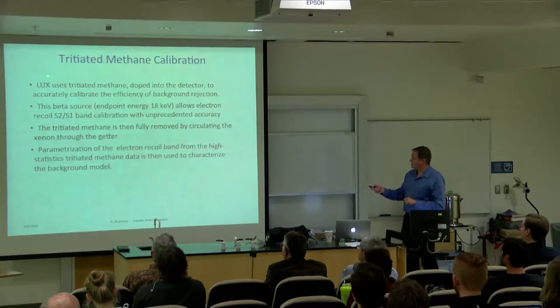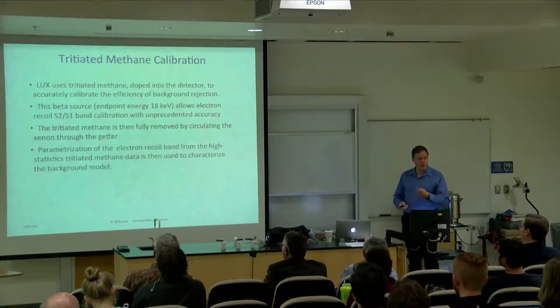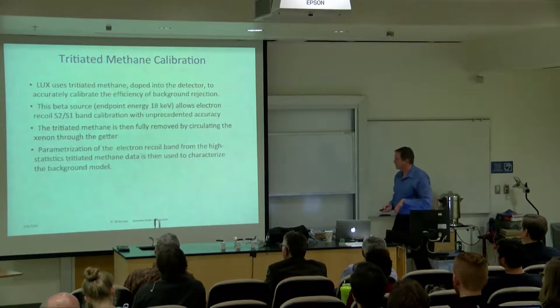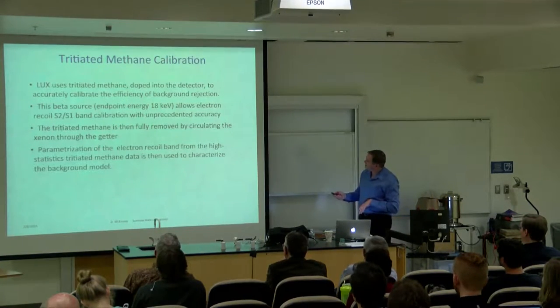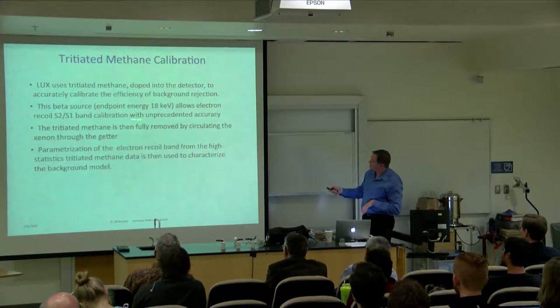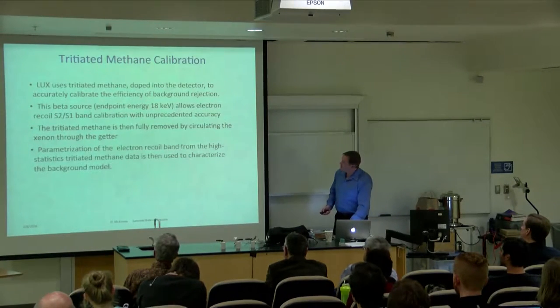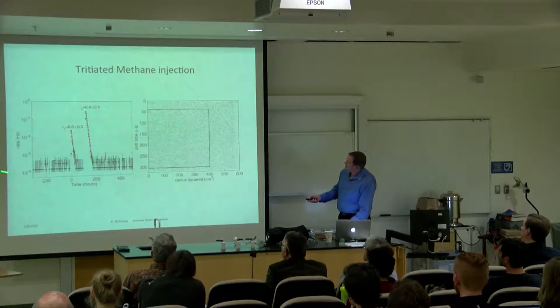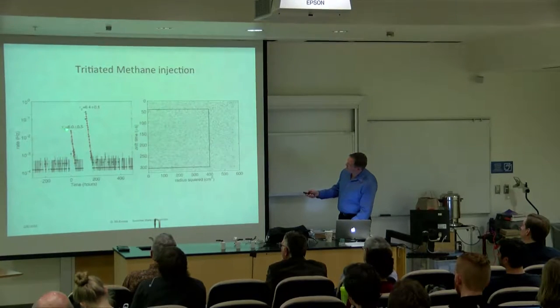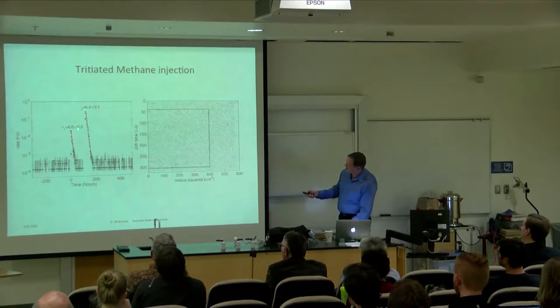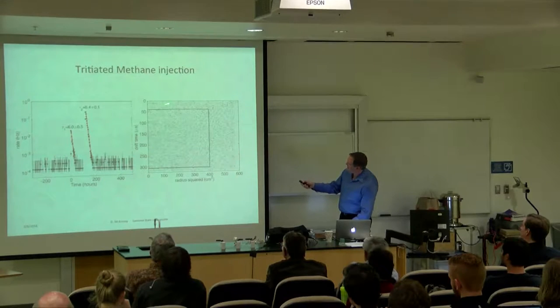We used tritiated methane, CH4, with one of the H's replaced by tritium. We could remove that by circulating the xenon through the getter. And that's what we did. Here we are: we put in some tritium, and then it decays away as the getter removes it. We wait some time, put it in again, and it decays away. Here's a map of events in the detector, where every dot is a tritium event.